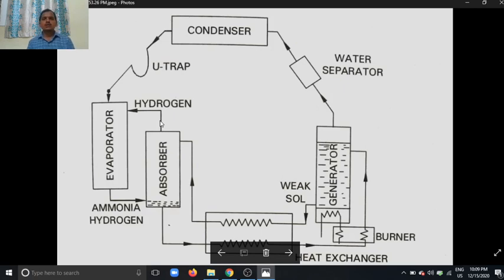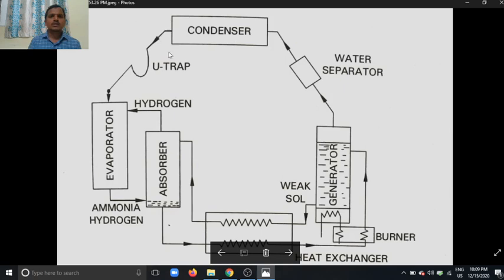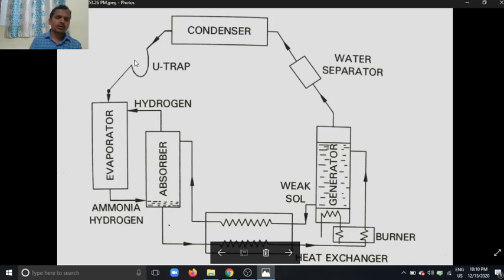In this Electrolux refrigeration system the main components are: condenser, U-trap, evaporator, absorber, heat exchanger, generator, and water separator. The U-trap acts as a one-way valve — it allows liquid refrigerant to pass into the evaporator, but does not allow gases such as hydrogen or ammonia vapor to go back to the condenser.